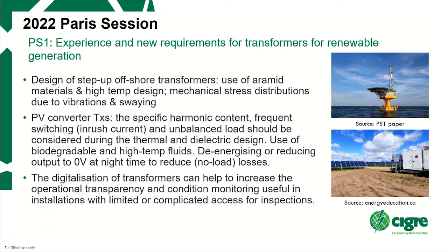In the design of converter transformers for solar applications, specific harmonic content, frequency of switching, and unbalanced loads all needed to be considered in the thermal and dielectric design of the transformers. There was also discussion on de-energisation - reducing the output of transformers to 0 volts at night in solar farm transformers to reduce no-load losses when the sun's not shining.